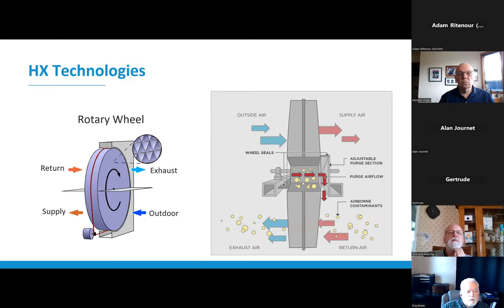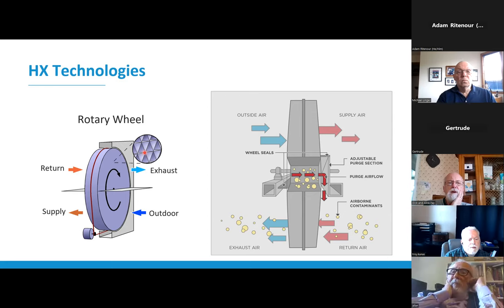All right, so I just want to go into those three different heat exchanger technologies a little more. So the first one is going to be the rotary wheel. With any exhaust air energy recovery system, there are two air streams, right? We've got the stale return air or the exhaust air coming out of the building, and then the fresh outdoor or supply air coming into the building. With this rotary wheel, you can imagine that this wheel is spinning clockwise very slowly. This wheel also has really small microchannels, usually made out of aluminum, and that's where the heat exchange is happening. Sometimes they're coated with a desiccant for latent heat transfer. And that's for the total enthalpy ERVs, not so much the HRVs.